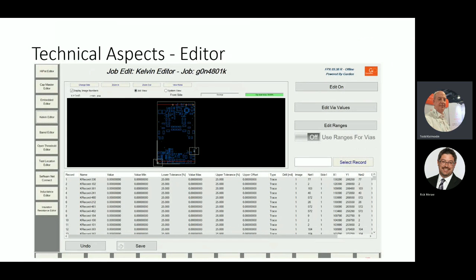Moving on - so when Rick was talking about the learn, compare, or learn master generation, once we have that created, we can go look at it. Most of the equipment out there, including ours, has the ability to go in and look at what the machine read and what your master values are. This is an editor screen where we show the record name for each of the measurements, the values, upper and lower tolerance.